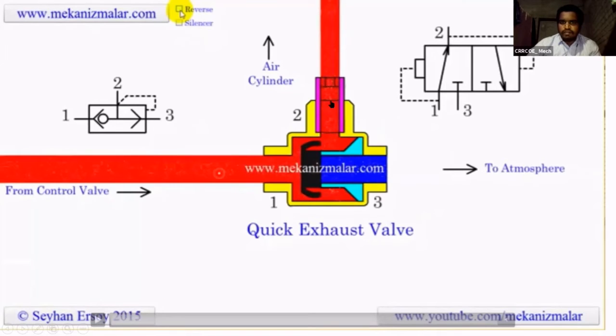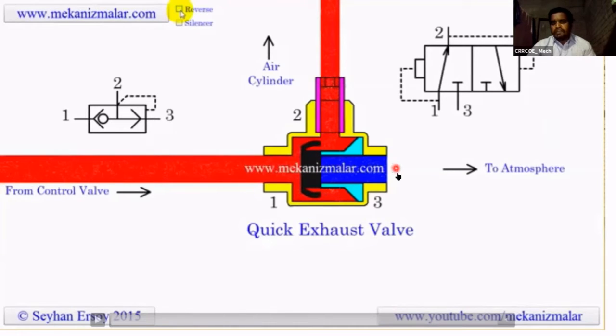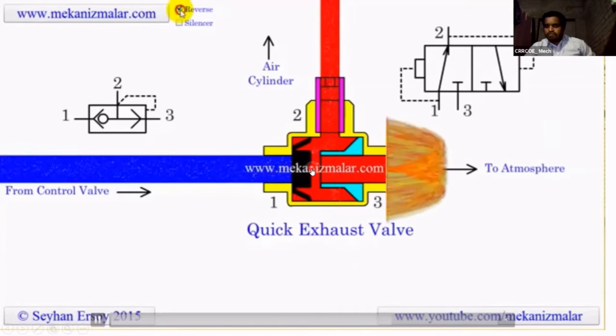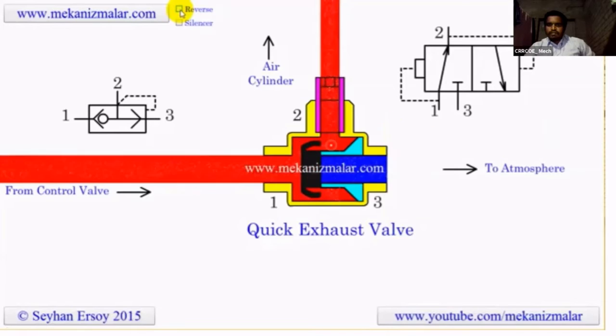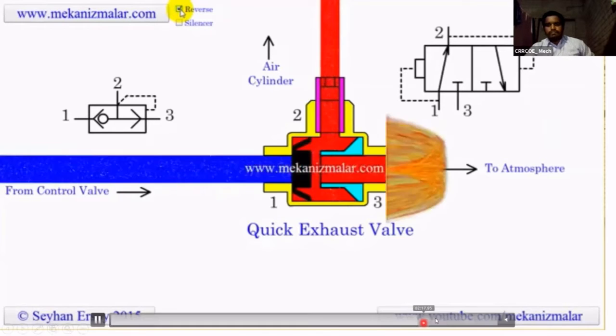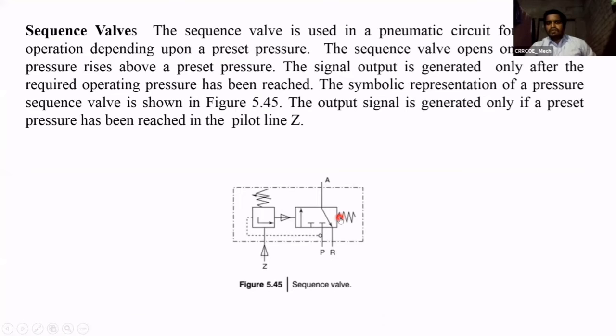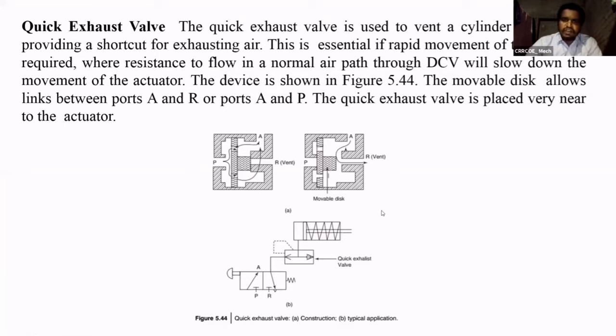Initially the air is moving through the direction control valve to the cylinder. If you want to remove the air quickly, removing it through the direction control valve takes time, so we use the quick exhaust valve as a shortcut. Just open this plug and the air moves towards atmosphere in a quick manner — it bursts towards atmosphere. The main purpose of the quick exhaust valve is to remove air from the cylinder in a shortcut way.